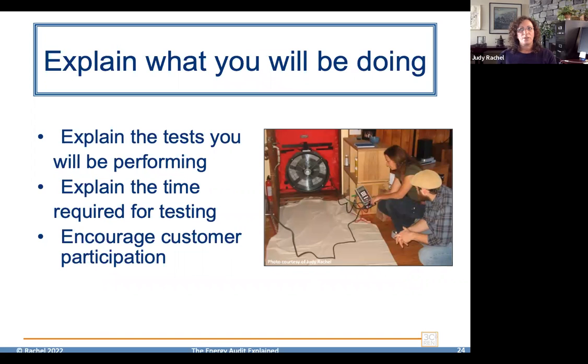It's important for us to explain what we're doing, including the tests we'll be performing and the time required for testing, which will come as a surprise to a lot of people. As a single individual doing an audit in somebody's home, it's going to take a minimum of 6 hours, and that's typically only if there's just a furnace and one water heater and no air conditioning. Otherwise, it's definitely going to take a full 8 hours for one person to do all the inspections and testing that needs to be done. If 2 people are going in to look at the home, that shortens the time to maybe 5 or 6 hours to get all the data collected. So it's a full day commitment just to do the inspection of the home.